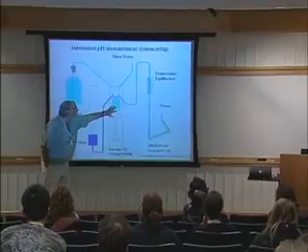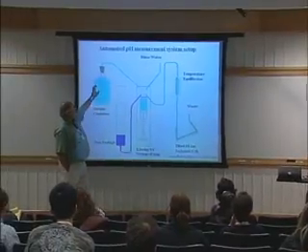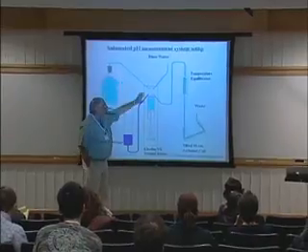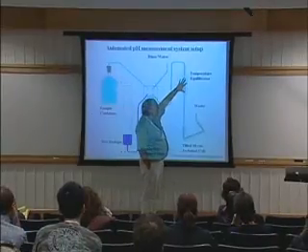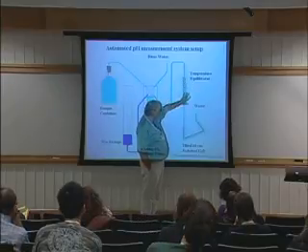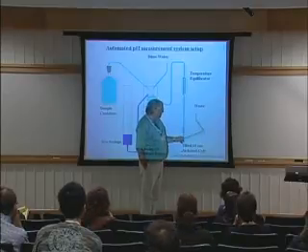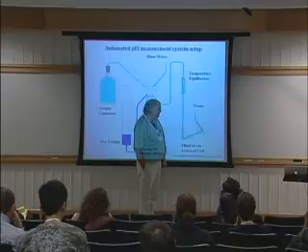We have a syringe pump. We can suck sample into the syringe pump and pump it on through here. This is a temperature equilibrator to ensure that it comes to the temperature we want to make the measurement at, and into a cell which is typically sloped a little bit so that any of your bigger bubbles move up to the end and come out. Little ones can hang around on the surface. This is a custom-made cell, so it's not straightforward to get hold of.